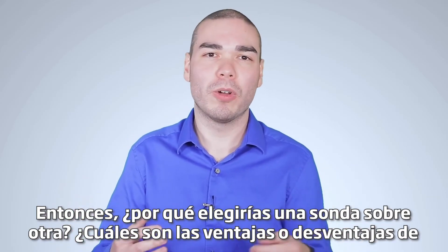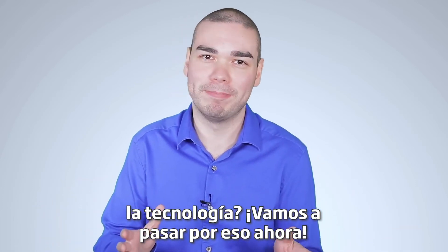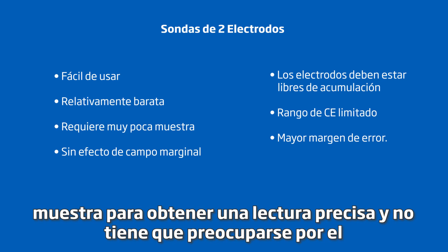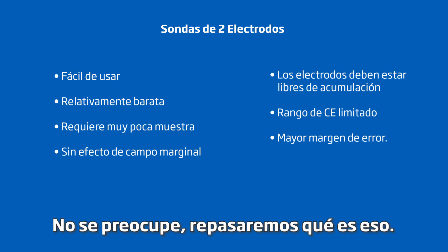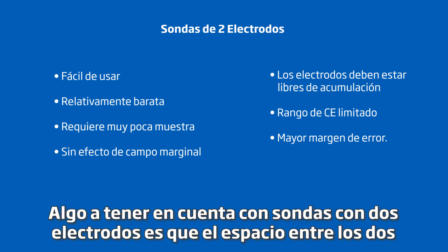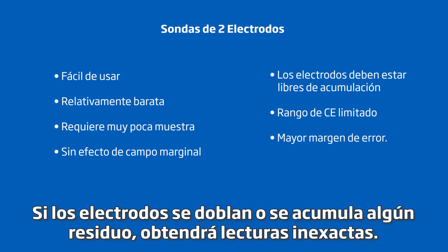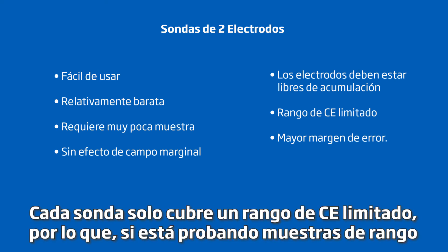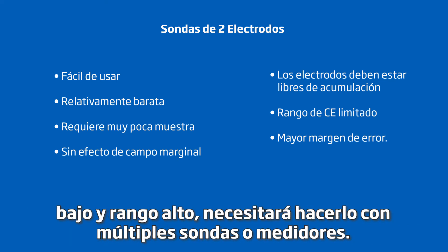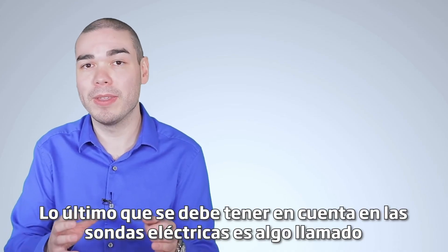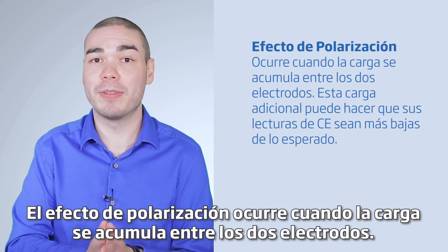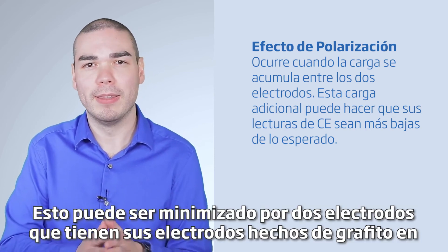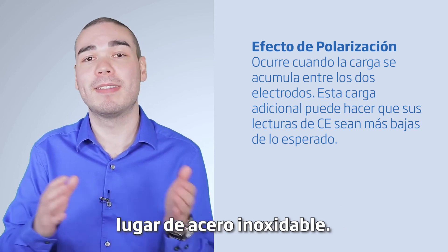So why would you choose one probe over another? Two electrode probes are easy to use, relatively inexpensive, require very little sample to get an accurate reading, and you don't have to worry about the fringe field effect. However, the space between the two electrodes has to be stable — if the electrodes get bent or a residue builds up, you will get inaccurate readings. Each probe only covers a limited EC range, so if you're testing low-range and high-range samples, you will need to buy multiple probes and or meters. Also be aware of the polarization effect, which happens when charge builds up between the two electrodes, causing EC readings to be lower than expected. This can be minimized by using electrodes made out of graphite instead of stainless steel.